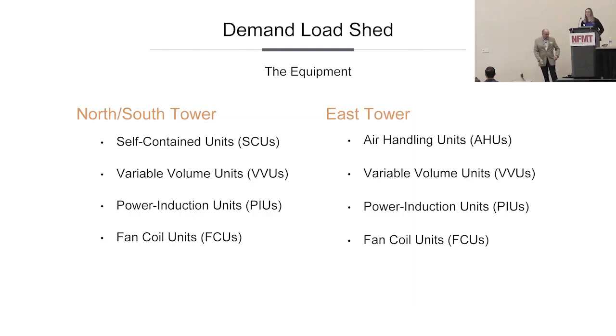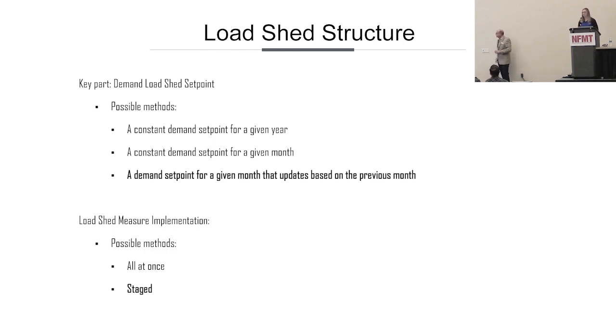All right. Okay, so this is my baby, so to speak. So we did demand load shed for Adtran that we mentioned a few times. Like I mentioned before, they have essentially two towers, that north and south tower and the east tower, all electric. I'm not going to read the slide. You can see what equipment they had in each of those buildings. So the first step was figuring out what exactly that load shed was going to look like. So we talked to that facility manager / energy manager at the building to see, okay, what kind of setup do you really want? And the end goal, I think, was let's do something that is relatively hands off. I don't want to have to go in and change the set point every month, every week, every year.